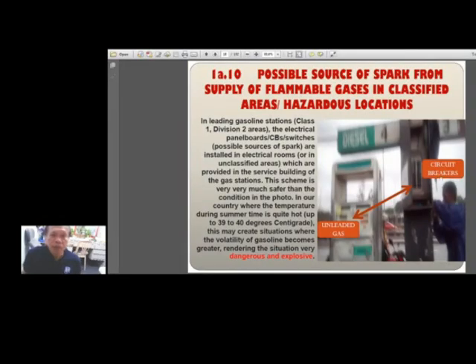Okay, I just want to show you that this is a wrong installation, where in a gasoline station, the owner, the contractor and the designer allowed the installation of a panel board with circuit breakers very close to a gas dispensing unit. This is a violation of the code. You do not install breakers very close to sources of flammable substances like the dispensing unit of a gasoline station. No way.